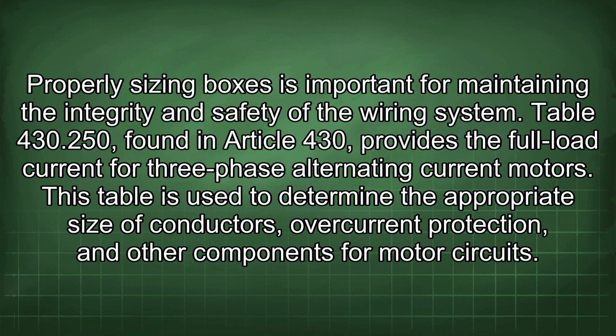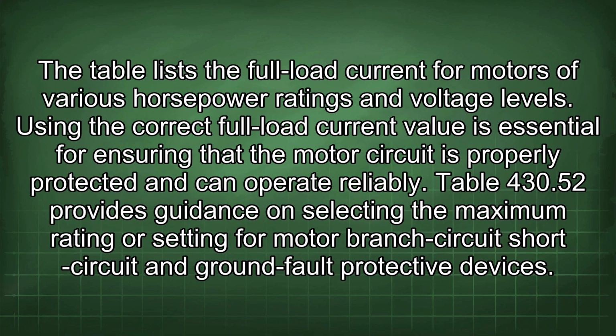Table 430.250, found in Article 430, provides the full load current for three-phase alternating current motors. This table is used to determine the appropriate size of conductors, overcurrent protection, and other components for motor circuits. The table lists the full load current for motors of various horsepower ratings and voltage levels. Using the correct full load current value is essential for ensuring that the motor circuit is properly protected and can operate reliably.